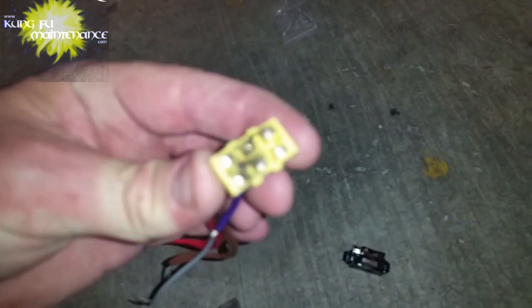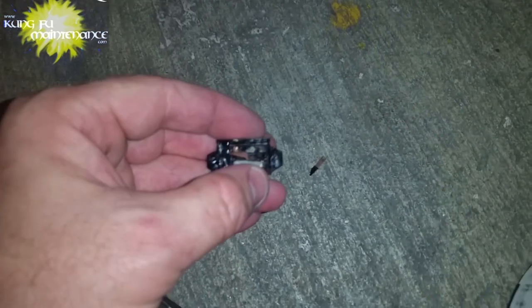Okay. I wanted to see inside this thing because I wanted to know what happened. So, let's see if we can tear this open. I've got channel locks or any number of other ways to get in there. Looks like a flat blade would do it. Everything but a flat blade. Here's a chisel. Oh, I did it. Oh, look at the contacts. The contacts are fried. Look at that. It's like the points or whatnot. Even that one just came apart.